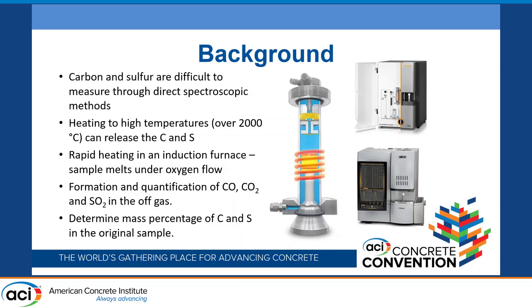Why has a technique been invented that's only going to measure carbon and sulfur? Well, these are two things that are kind of difficult to measure — you often will have difficulty quantifying these through a direct spectrographic method. These benchtop devices basically contain an induction furnace. You take a sample, raise it into that induction heating zone, and it heats up very rapidly to about 2,000 degrees. You drive off everything out of the sample that's going to fly off at that heat. With oxygen flowing through the furnace, any carbon driven off will form carbon monoxide or carbon dioxide, and any sulfur driven off will form sulfur dioxide, and those can be picked up by an infrared sensor and quantified.